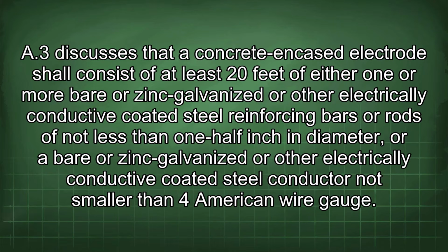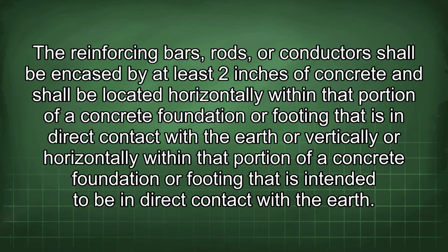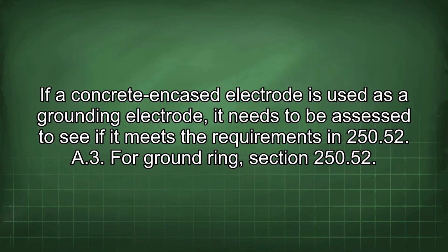(A)(3) discusses that a concrete encased electrode shall consist of at least 20 feet of either one or more bare or zinc galvanized or other electrically conductive coated steel reinforcing bars or rods of not less than 1/2 inch in diameter, or a bare or zinc galvanized or other electrically conductive coated steel conductor not smaller than 4 American wire gauge. The reinforcing bars, rods, or conductors shall be encased by at least 2 inches of concrete and shall be located horizontally within that portion of a concrete foundation or footing that is in direct contact with the earth, or vertically or horizontally within that portion of a concrete foundation or footing that is intended to be in direct contact with the earth.